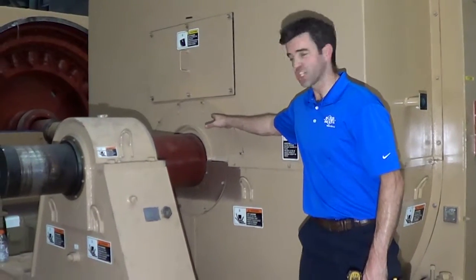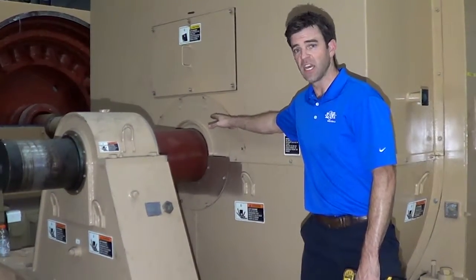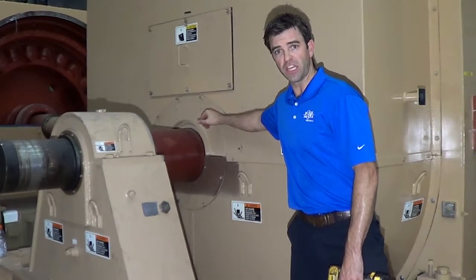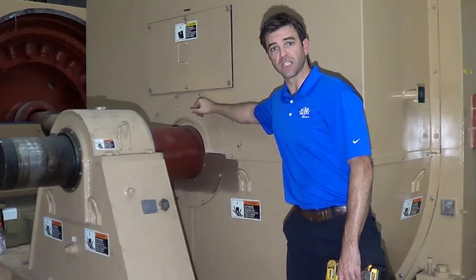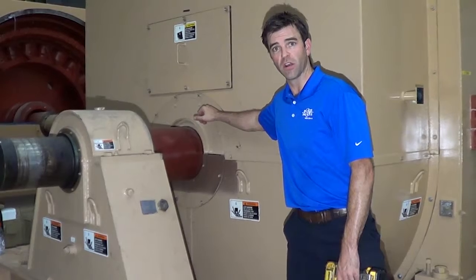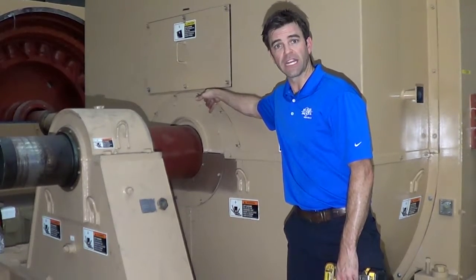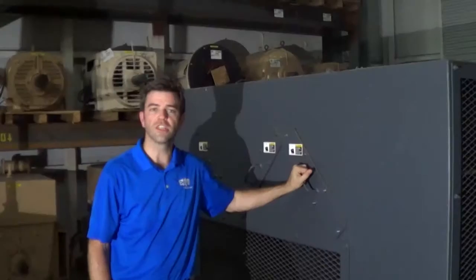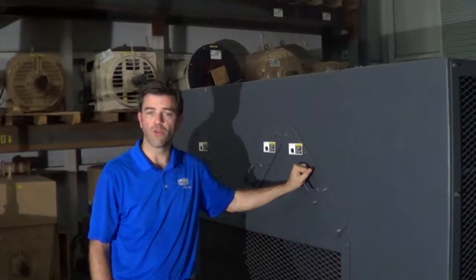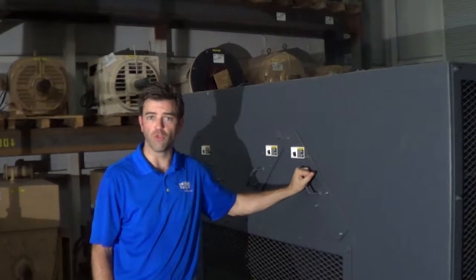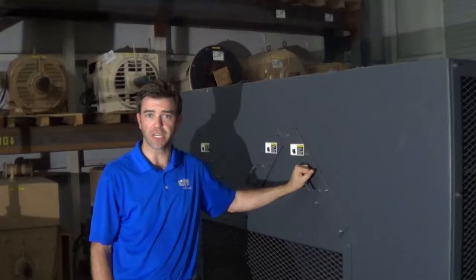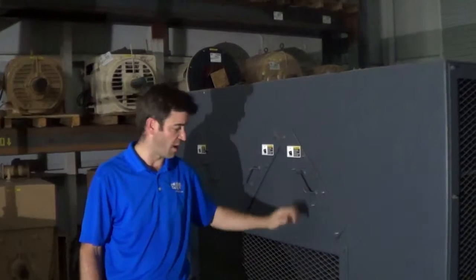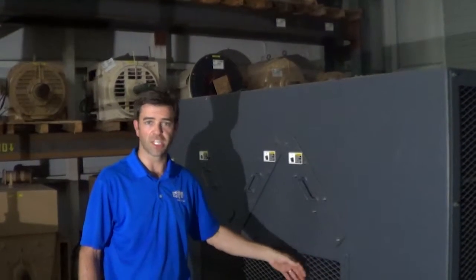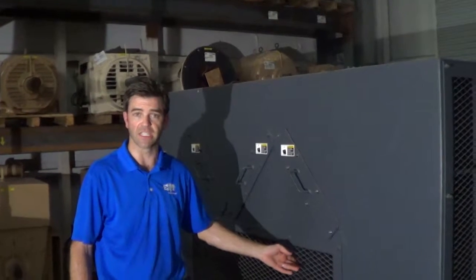Once you finish reinstalling covers and gaskets, apply a bead of RTV on all upper surfaces, such as the air seal shown here, to prevent water from migrating into the motor. Now let's talk about filters. Some rotating equipment is installed with WP1 or ODP covers, which don't have any filters and have only a set of screens. These can be quickly inspected and cleaned as necessary.